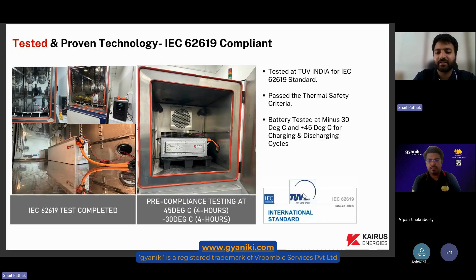These battery systems have been tested for the thermal propagation test, which is the destructive testing that has to be conducted, and most customers are also happy if you're doing these tests. Apart from that, these battery systems are tested at minus 30 degrees Celsius - an entire charging discharging cycle has been done at minus 30 degrees and plus 45 degrees.